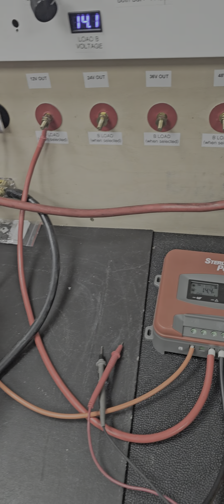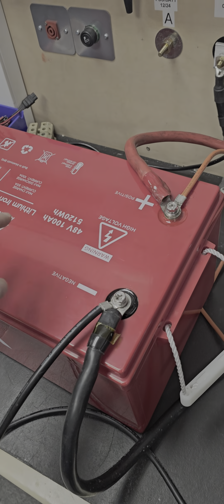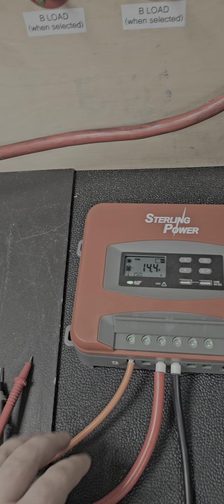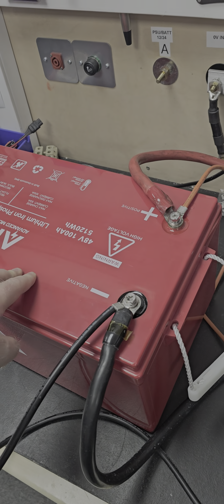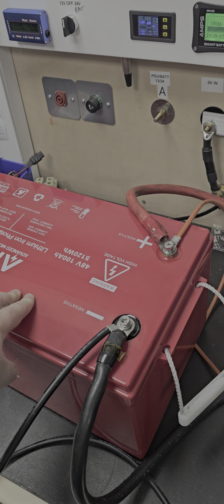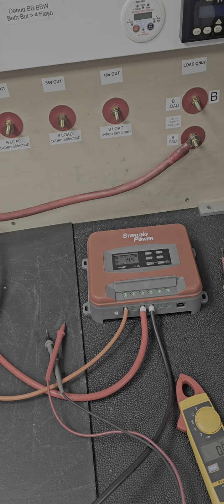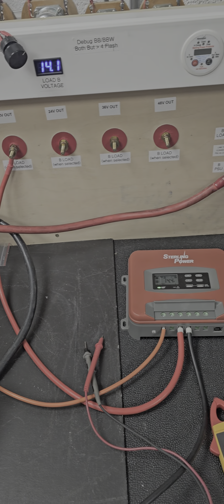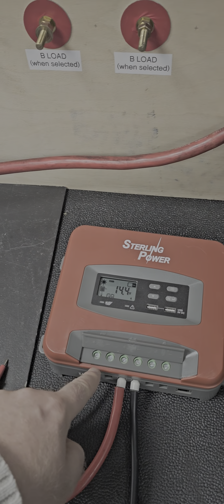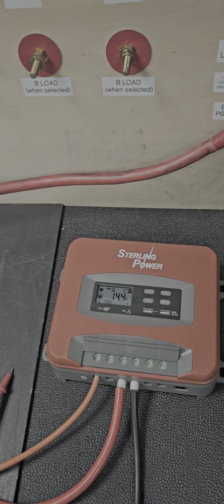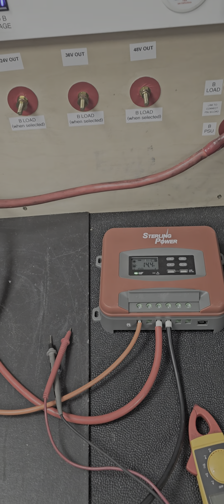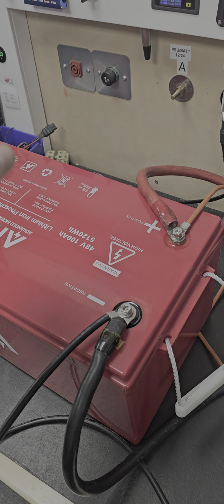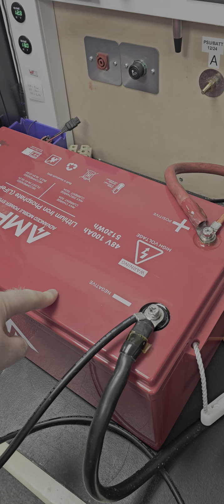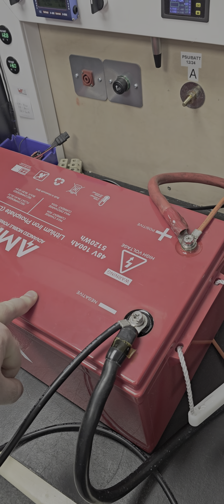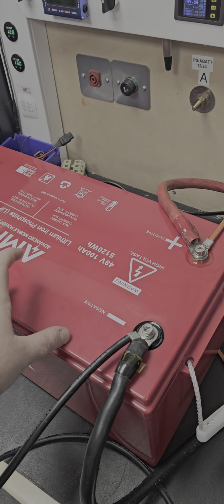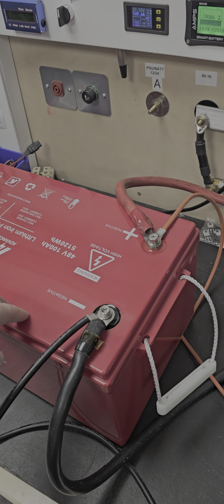The caveat with this is, for as long as it's connected to a 48 volt feed, it will carry on dragging that 48 volt battery down to as low as empty if there's enough demand in the 12 volt battery to accept power. There's no turning off mechanism - provided it sees voltage here, it will buck that power down to keep your 12 volt battery topped up. I am, however, predicting that if you've got a 48 volt system, there's probably high power and a lot of storage there, with constant 48 volt charge or discharge going into it - these batteries have probably got surplus energy to meet that demand anyway.